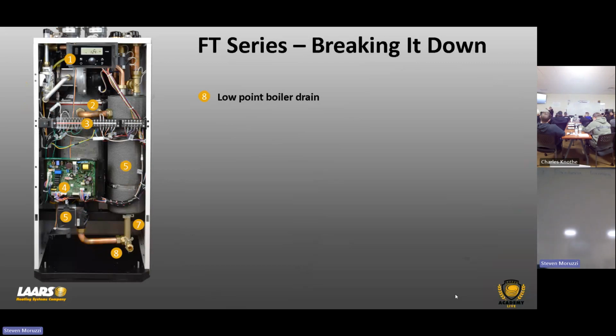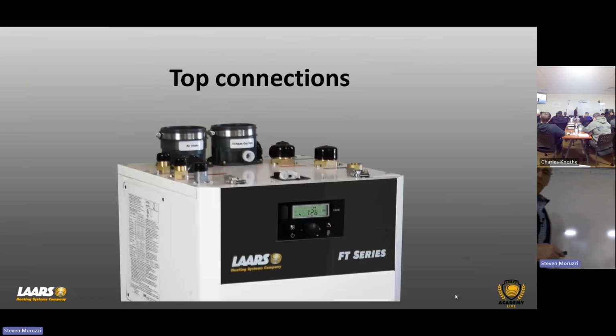And if you ever had to replace or remove that pump, obviously you're going to isolate, ball valve your boiler, drain it off, and then these are quick connects. Quick connect, take this connection off the pump, and you could slide that right out. You'd have to refill the boiler afterwards, but it is serviceable from the front. Okay. So top connections here.